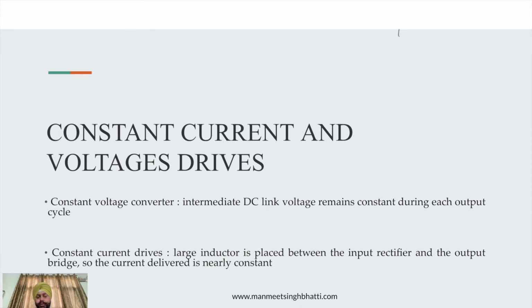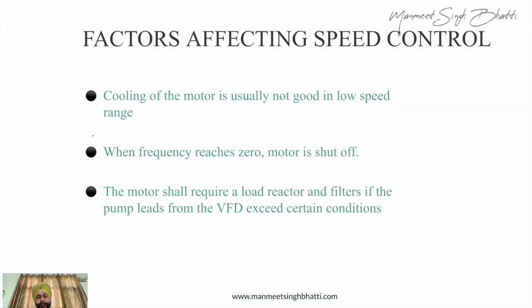Now constant current and constant voltage drives, what we have seen is basically that most of the time the VFD switching is controlled, and we already have one DC link in between for the smoothing of the curve. So you can control the voltage, and you can also control the current going out of that VFD. That way you are able to control the amount of power being fed to the motor. So that is the real control that you can get with the VFDs.